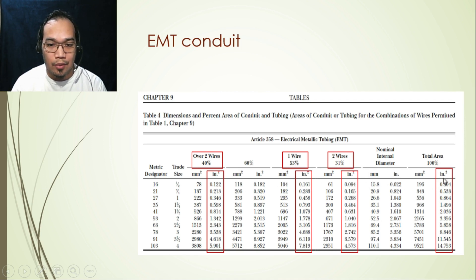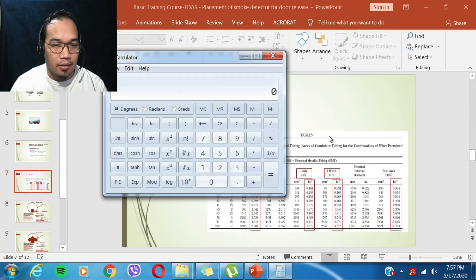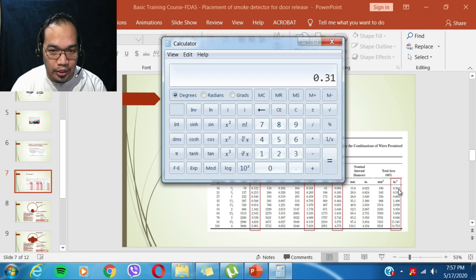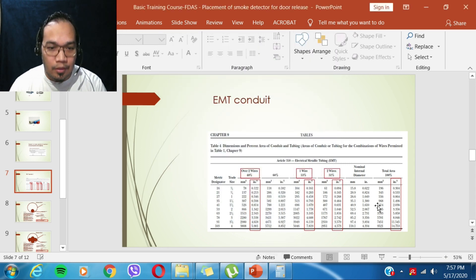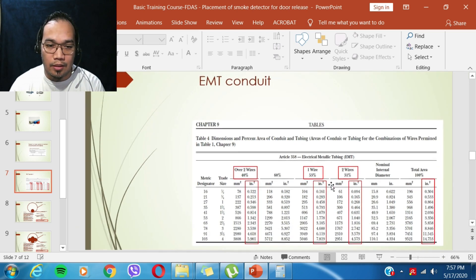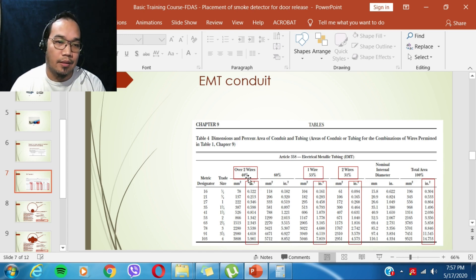For example, the total cross-sectional area of a 1/2 inch EMT conduit is 0.304 square inches. To find the allowable fill for two wires, we calculate 31% of 0.304, which equals 0.094 square inches. That is where the value in the table for one-half inch conduit with two wires comes from. For one wire it's 53%, and so on.